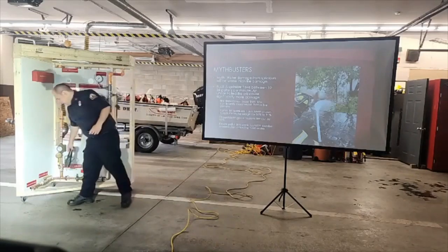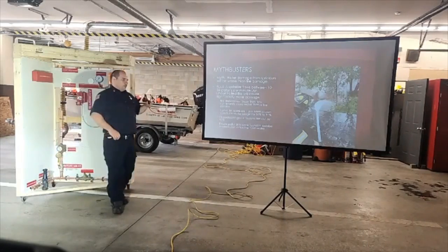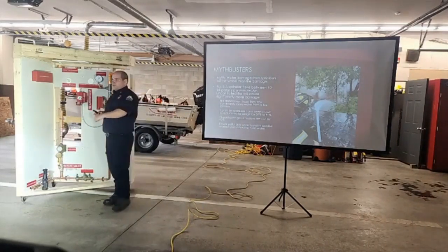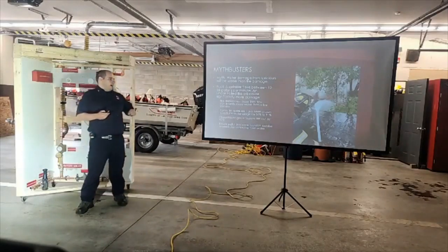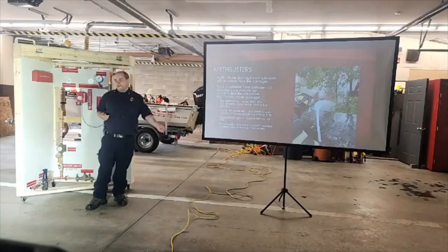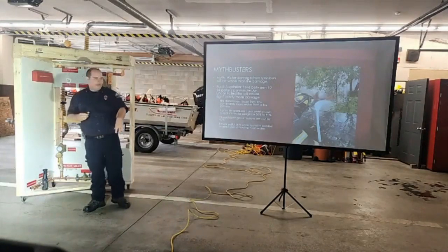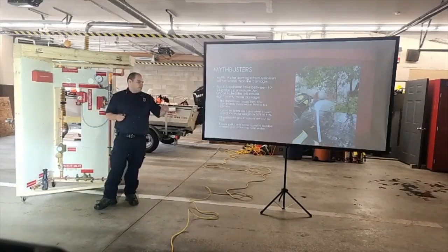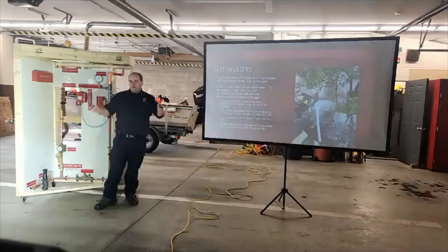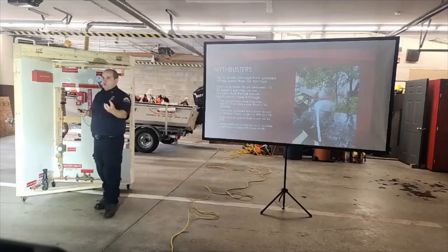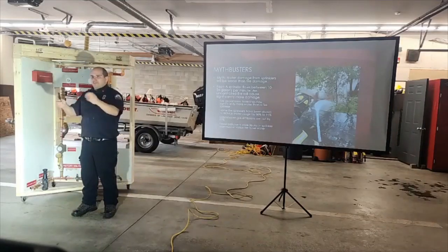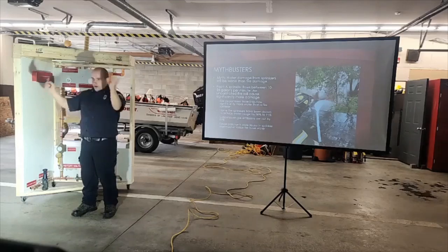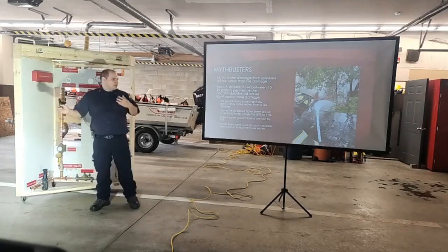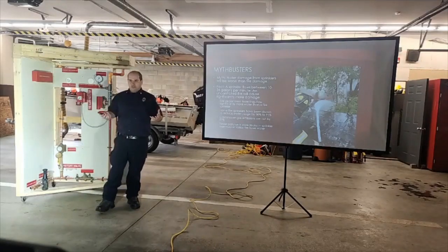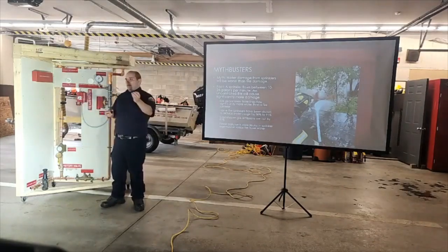FM Global did studies on water damage from fire sprinklers. They show home fire sprinklers generally reduce the water usage needed to control a fire by 50 to 91%. It also cuts greenhouse gas emissions by 97%, because instead of letting smoke vent into the environment, it's controlled while the fire is small. They even studied runoff water from fires with sprinklers versus without, and found very few contaminants in the runoff because the fire is controlled before it burns more material. When we arrive with the fire department, we're putting 185 gallons a minute into your house, and all that water runoff contains bad pollutants and carcinogens we don't want people exposed to. So sprinklers aren't just life-safety and property friendly, they're environmentally friendly too.